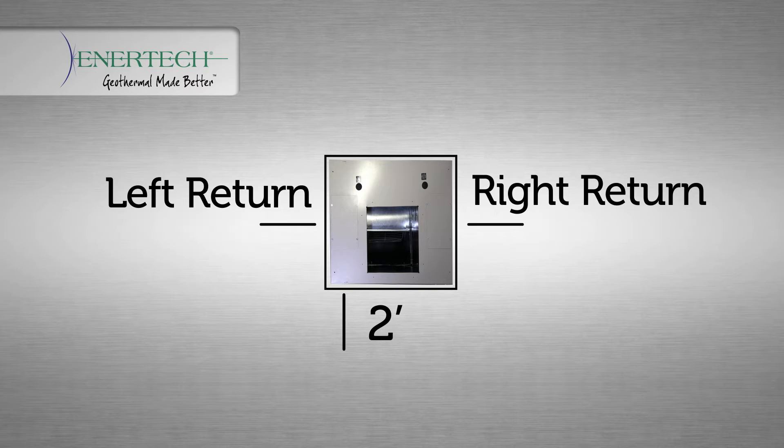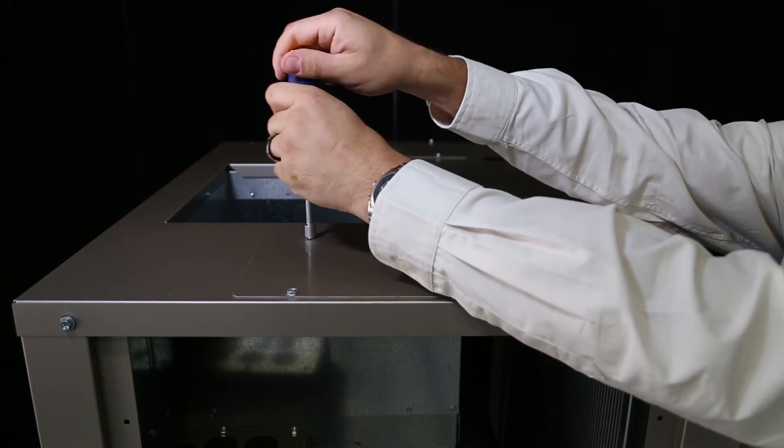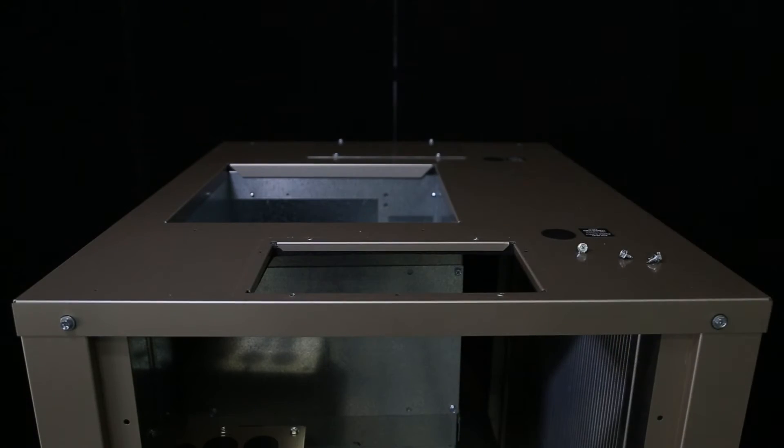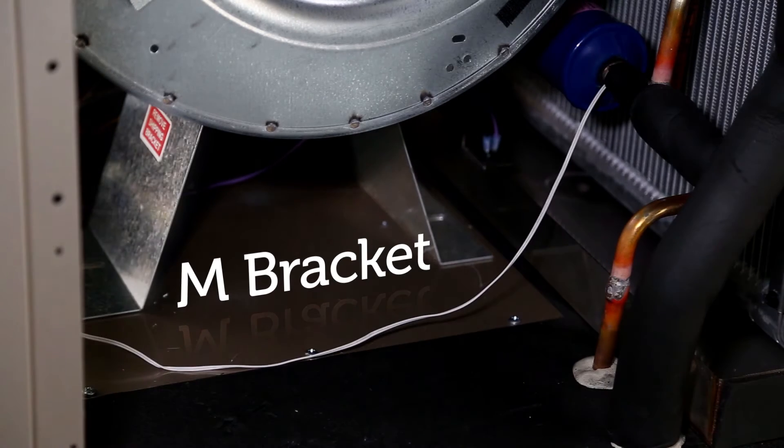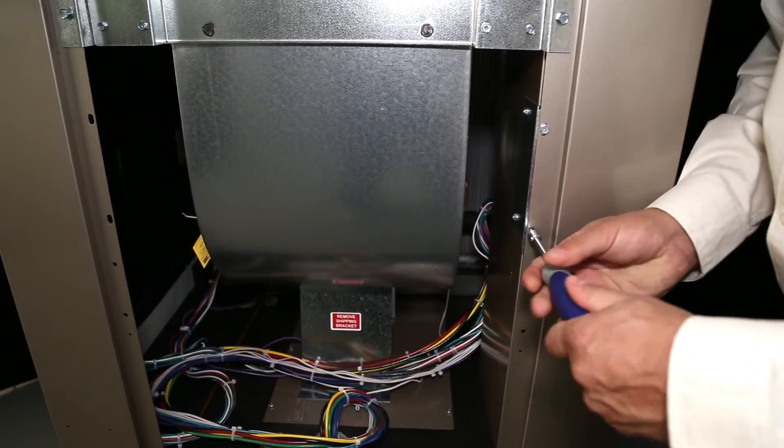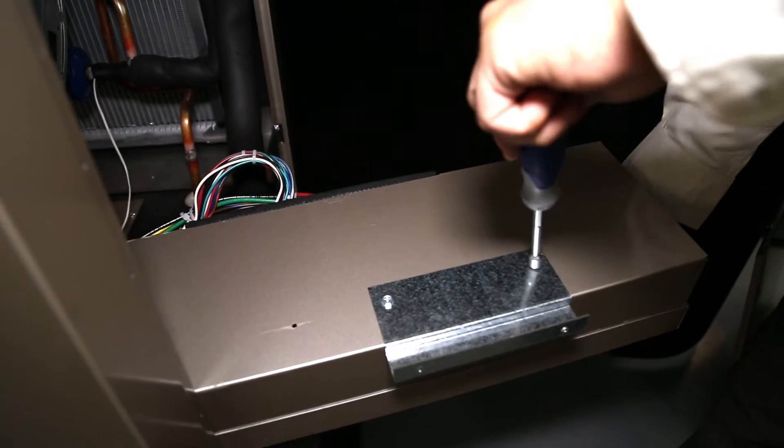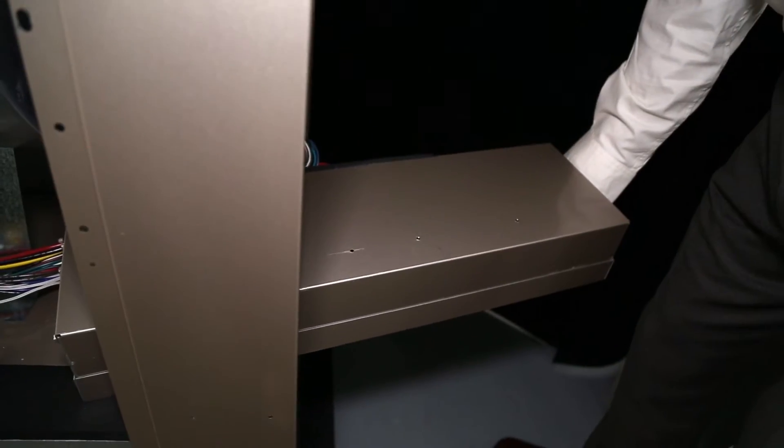Once you have determined whether the unit will be left or right return, we'll install the control box. Mounting the control box requires removal of the top access cover port filler plate in front or back, several panels and the M bracket under the blower housing. Make sure to keep the four screws for future use. Remove the control box shipping bracket from the unit and the control box. This requires the removal of four screws. Remove the bracket from the unit. It can be recycled.